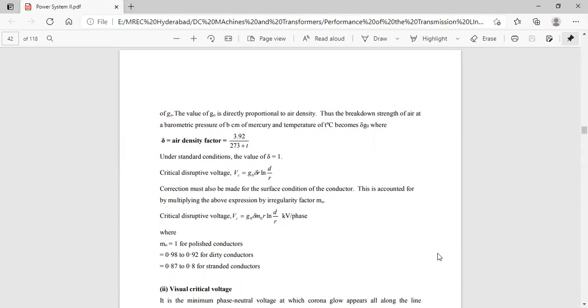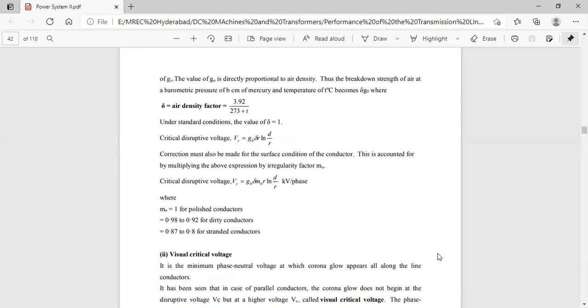Correction must also be made for the surface condition of the conductor. This is accounted for by multiplying the above expression by the irregularity factor m naught. Now, the modified critical disruptive voltage Vc equals g naught into delta into m naught into r into ln of d by r kilovolt per phase, where m naught is equal to 1 for polished conductors, 0.98 to 0.92 for dirty conductors, and 0.87 to 0.8 for stranded conductors.